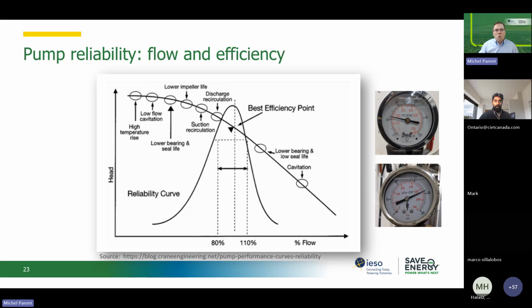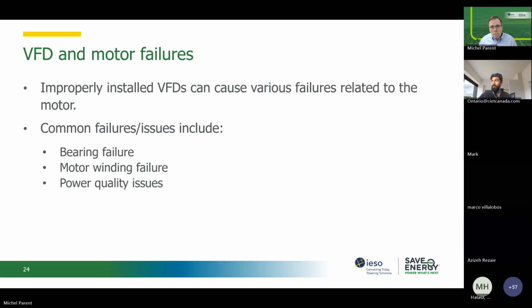My colleague, Stephen Dixon, always says, show me your least reliable pump. The one where the bearing goes all the time, the one where the seals are always leaking, that pump is oversized. So make sure that part of your PM is to verify that the pressure drop across your pump matches the nameplate. If it doesn't match the nameplate, you can throttle it, which is not very energy efficient. Ideally, you put a VFD on it, and then you can run in that sweet spot where it will be efficient and reliable. So that graph will show what happens in terms of the reliability of your pump if your head is too high or too low.